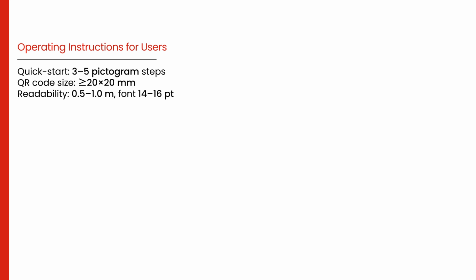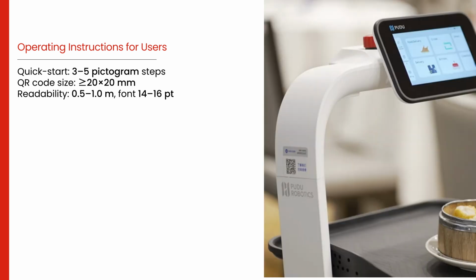Operating instructions for users must be simple and fast to understand. The HMI should show 3 to 5 pictogram steps, supported by a QR code of at least 20 by 20 mm, with on-screen text readable at 0.5 to 1 meter using 14 to 16 point fonts.